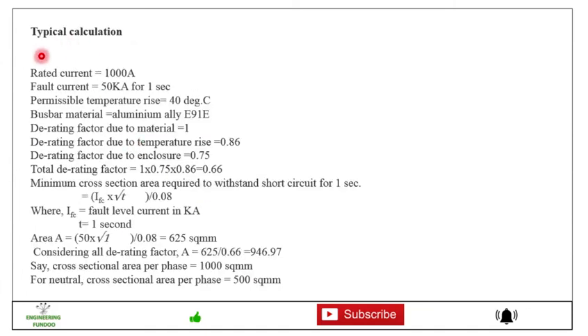Now for typical calculation for busbar area. Let's say rated current is 1000, fault current is 50 kA for one second, permissible temperature rise is 40 degree, that is the requirement. Busbar material is aluminum. Now derating factor due to material is 1, derating factor due to temperature rise is 0.86, and derating factor due to enclosure is 0.75. These are the available condition and data requirement for calculating the busbar.